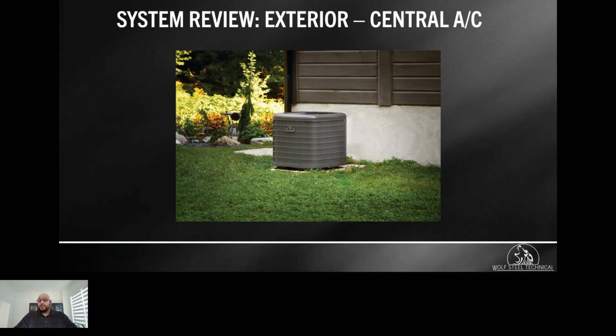My recommendation is to replace the copper lines, but that's not always the case in some scenarios. If you do have to reuse the lines because of the location of the furnace in the finished basement, make sure that you take your time to properly flush them using the appropriate kit.